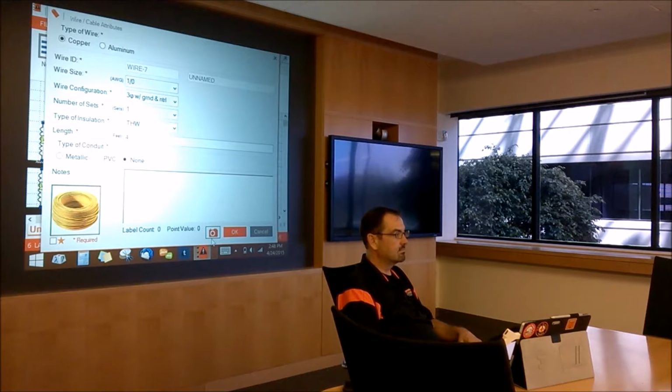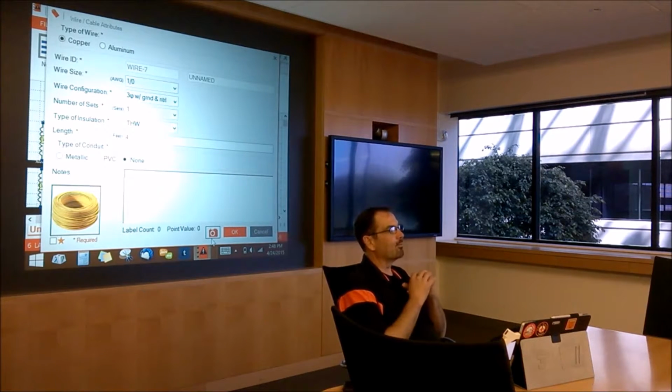And the way we manage work is typically we'll do as much of the non-invasive investigation that we can, and then we'll either utilize the facility electricians or sometimes we're working with outside contractors. So there's really a two-stage data collection. We'll gather as much as we can, figure out the general arrangement of the one-line diagram, and then where you've got to open something up, now we need an electrician. Yeah, that's what I was going to say. Going in at the point where you're into live equipment, now we're having them confirm, hey, we took a wire size off the existing one-line, can you confirm that it's really number 4, or whatever.